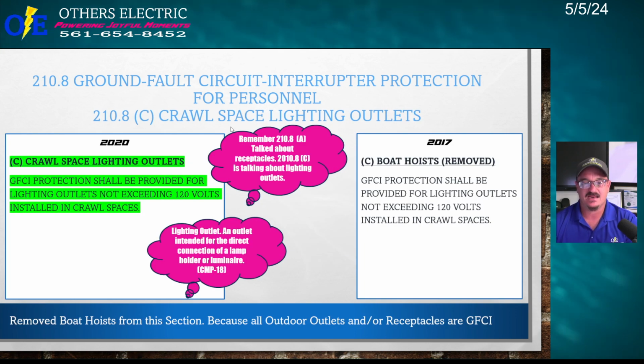All right. They added 210.8C, crawl space lighting outlets. Okay? So 210.8C was added. GFCI protection shall be provided for lighting outlets not exceeding 120 volts installed in crawl spaces. Not a Florida thing, crawl spaces, but if you've got lighting outlets in there, they now have to be GFCI protected. Okay? So I just want you to remember, 210.8A talked about receptacles. 210.8C is talking about lighting outlets. Lighting outlet, an outlet intended for the direct connection of a lamp holder or luminaire. So that's what they're talking about. If you're in a crawl space and it's for a lighting outlet, that now has to be GFCI protected, okay?